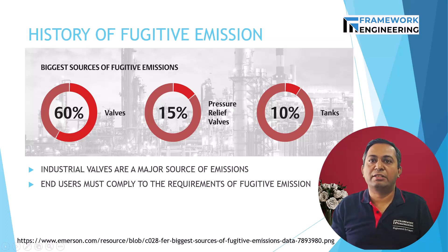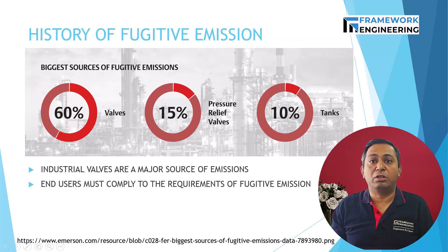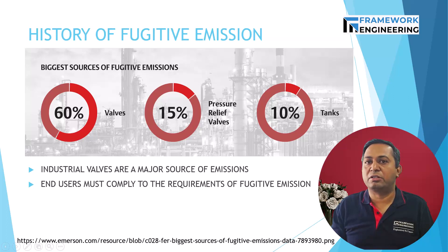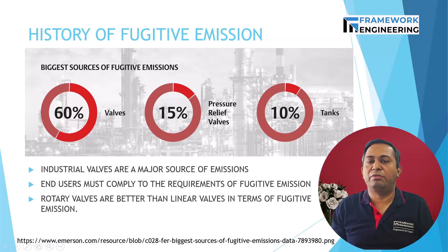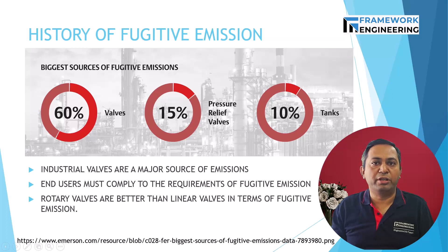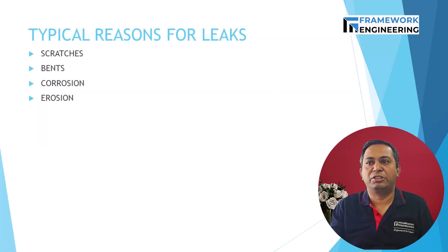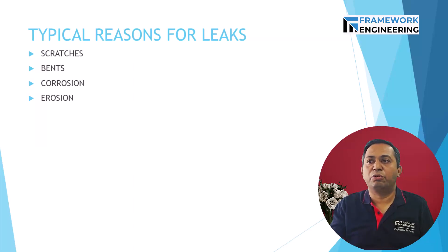Valve sizing is also critical in any system because it determines not only the amount of flow but the volume of flow. If the valve is not sized properly, it may fail to completely close and connect seamlessly with other system components, resulting in leaks. Within valves themselves, the linear globe valve represents around 70 percent of total leaks — linear valves are more prone to emissions compared to rotary valves. The four major typical reasons for leaks are scratches, bends, corrosion, and erosion.